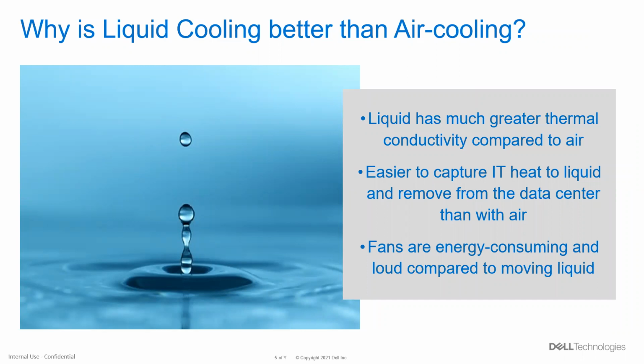So why liquid cooling? Well, air is a fluid, and it captures heat. It's just that liquid captures heat much more effectively than air. So by capturing the heat more easily, keeping that heat energy in the liquid through heat transfer to the facility water loop, it's much more effective at capturing and removing that from the data center environment. And the last thing to point out is, as most people who've been in data centers know, IT fans spinning very fast generate a lot of noise and will pump out a lot of heat into the hot aisle of data centers. So shifting that to liquid not only is more effective, but it makes for a more pleasant experience for people actually working in the data center environment.